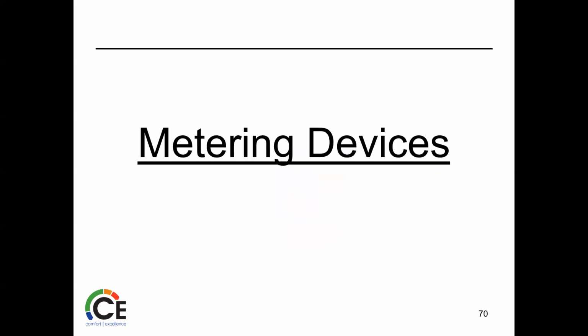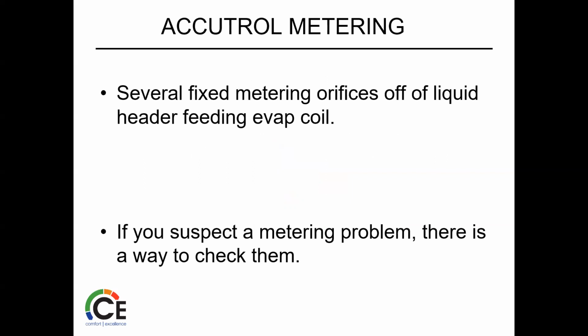All right, metering devices, commercial units. So the biggest one that you run into that throws everybody off is what they call the Accutrol device. It has a bunch of fixed orifices off the liquid header feeding the evap coil. If you think that this device, its metering device, is bad, there is a pretty simple way to check it. It is not a serviceable thing, a lot like a TXV. A TXV either works or not. This is the same way.